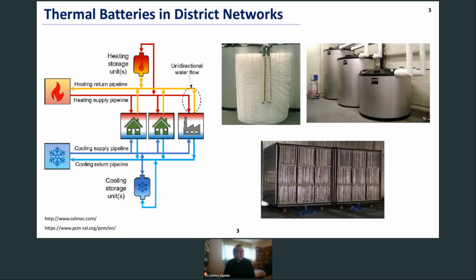The top right photo shows three ice storage tanks of different dimensions. The interesting thing happens inside: the tank is filled with liquid water, but there's an arrangement of spiral tubes made of polyethylene, where a heat transfer fluid, in this case a refrigerant, circulates. If the temperature of this refrigerant is below 0 degrees, ice will grow. If a warm heat transfer fluid is then circulated, the ice will melt.